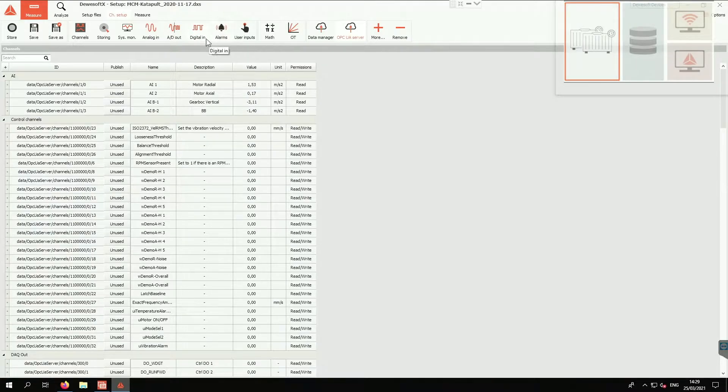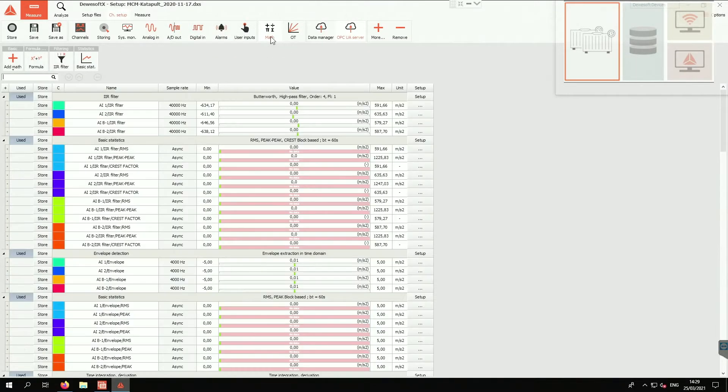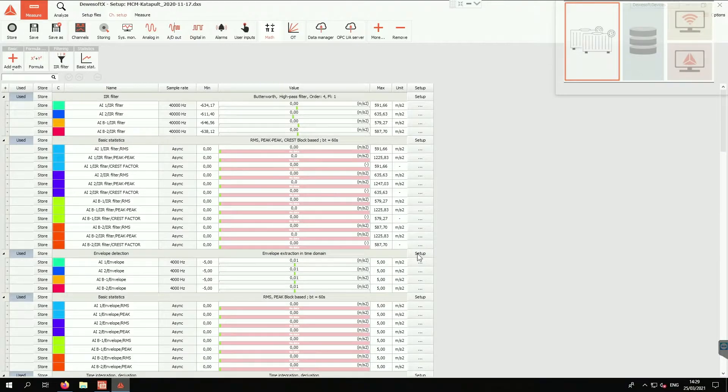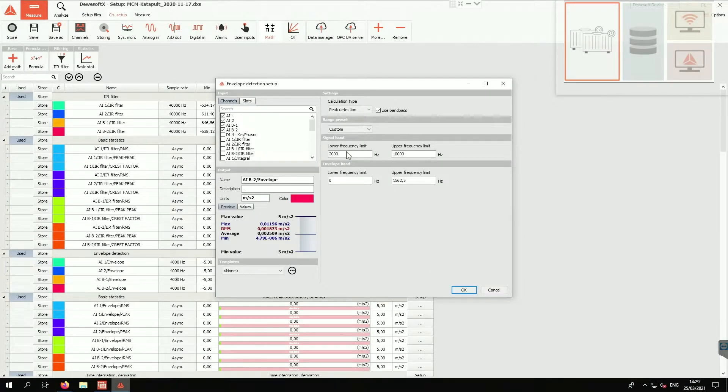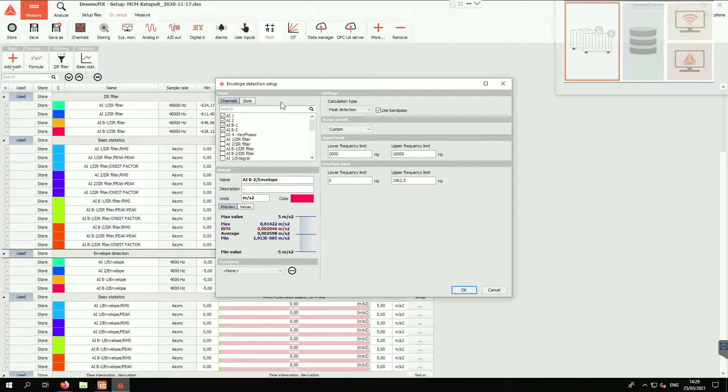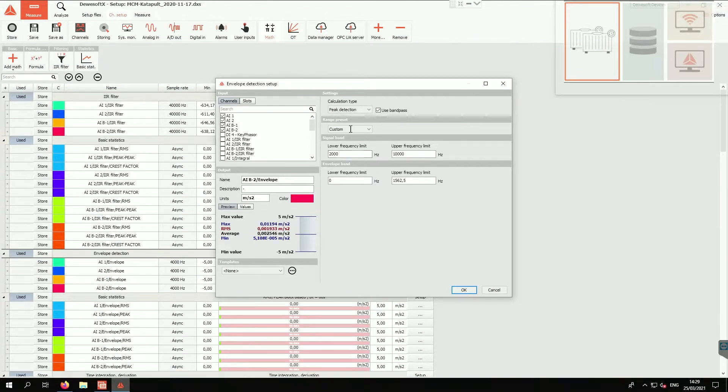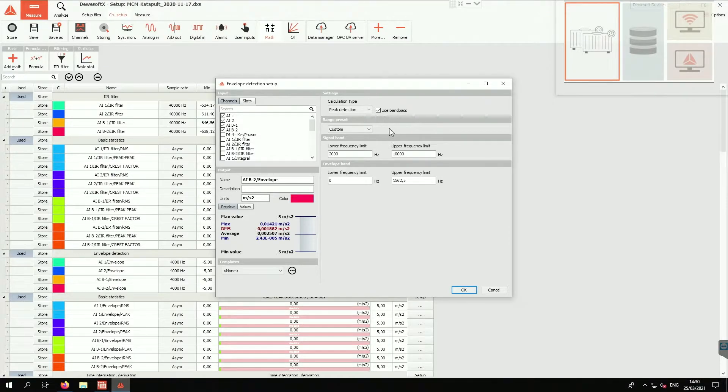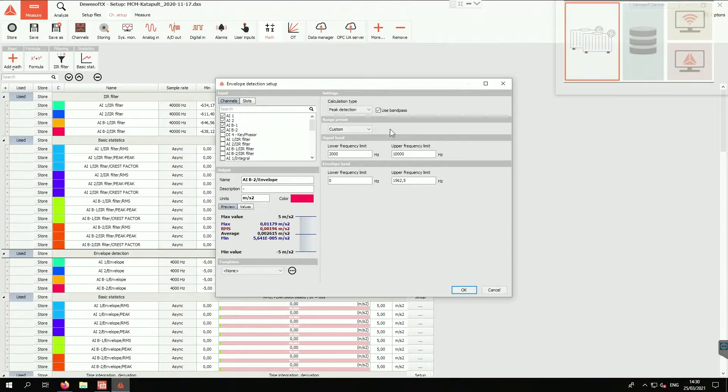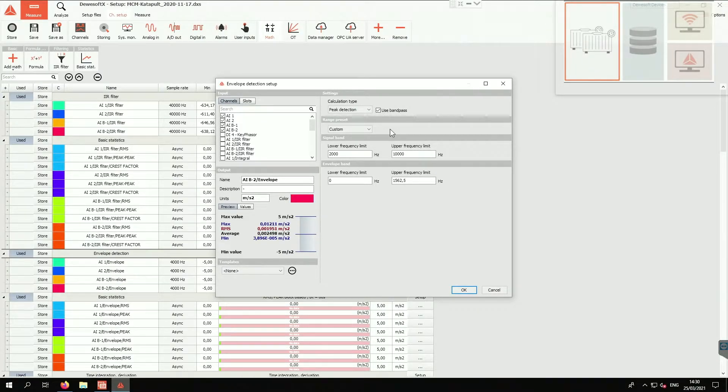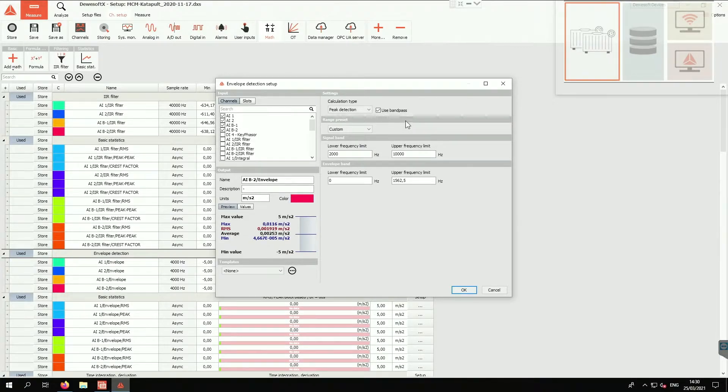First of all, we do the envelope detection. This is a math module, so it's this one. We do envelope extraction in time domain of the acceleration signal, so we get directly 40 kilosamples in and we get out the envelope signal which basically filters the low frequency noise and only focuses on these peaks, the spikes in the time signal. The spikes have a high frequency, and then you want to see how fast these spikes actually repeat themselves, and that's how you get the bearing frequencies.